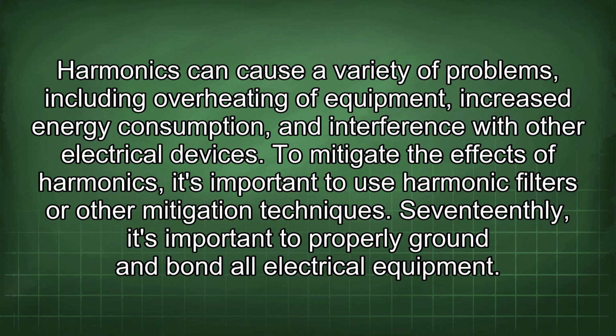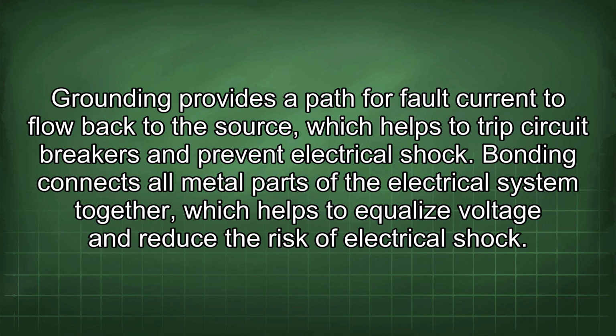17thly, it's important to properly ground and bond all electrical equipment. Grounding provides a path for fault current to flow back to the source, which helps to trip circuit breakers and prevent electrical shock. Bonding connects all metal parts of the electrical system together, which helps to equalize voltage and reduce the risk of electrical shock.